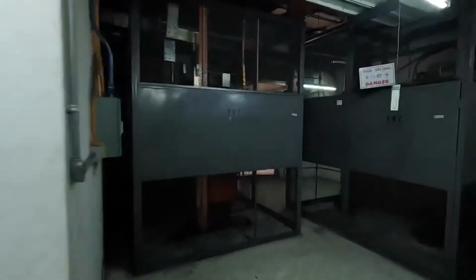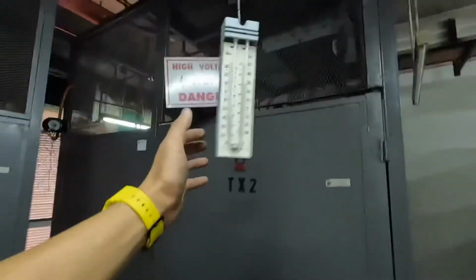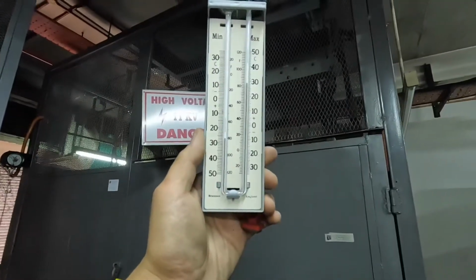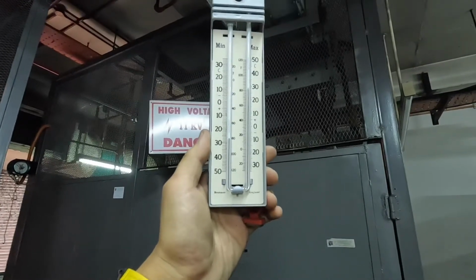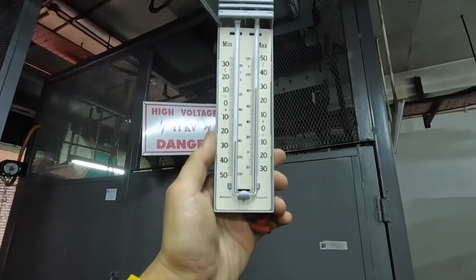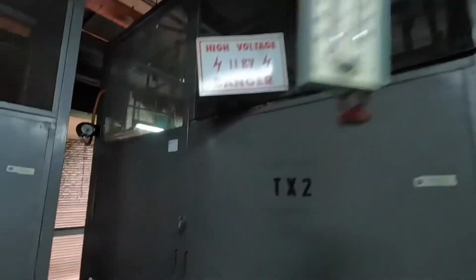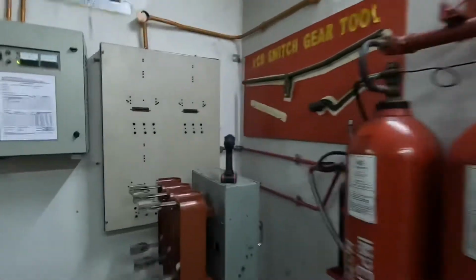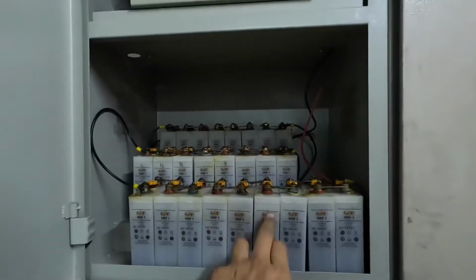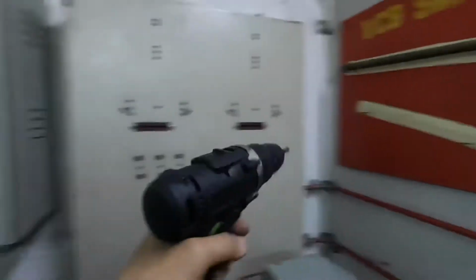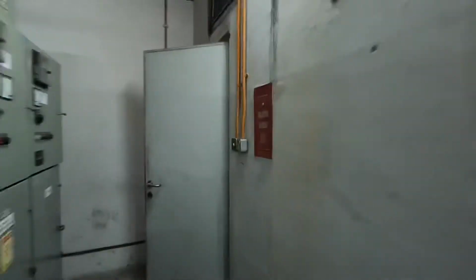And here we have 2 units of cast resin transformer. Currently the temperature is room temperature, I mean, not warm. Maybe 25, 26, 27. Temperature controller also faulty, need to replace. Okay, battery okay, just service. Electrolyte level a bit drop. Okay, let's proceed to the LV room.